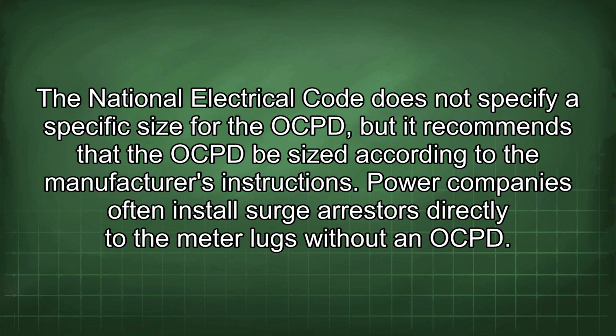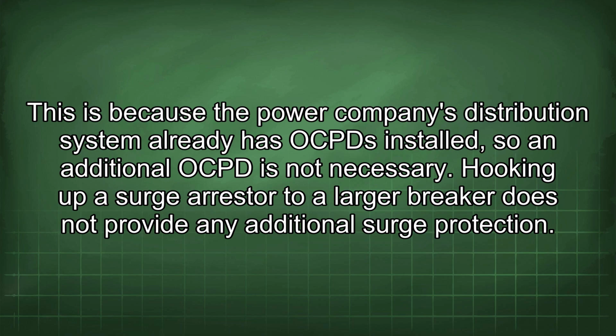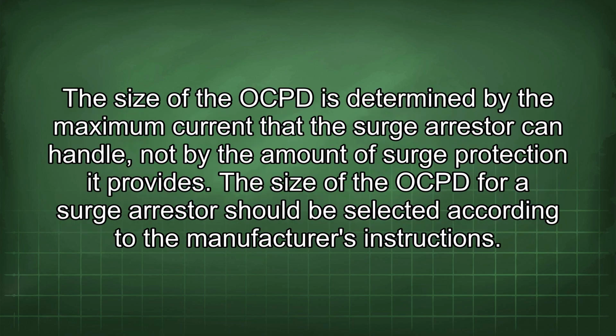Power companies often install surge arrestors directly to the meter lugs without an OCPD. This is because the power company's distribution system already has OCPDs installed, so an additional OCPD is not necessary. Hooking up a surge arrestor to a larger breaker does not provide any additional surge protection. The size of the OCPD is determined by the maximum current that the surge arrestor can handle, not by the amount of surge protection it provides.